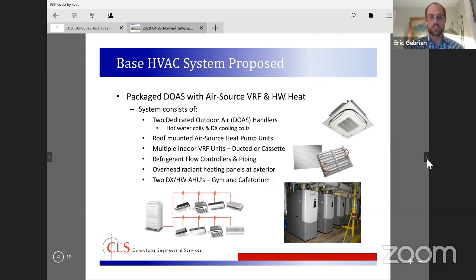Because we're directly ventilating and then directly exhausting each of the classrooms. VRF simply stands for variable refrigerant flow. If you're familiar with a Mitsubishi ductless split that you might have in your house, or Daikin is another company that makes them, you have a unit on the wall that does heating and cooling, and a unit outside that pairs with it. This is basically a much larger commercial version of that same system. We have multiple indoor units, one for each classroom, and multiple outdoor units that work together. That's the system we're using more and more these days because it's become extremely efficient at heating and cooling, far more efficient than existing systems in schools that are 10, 20 plus years old. It's got great turndown for part load heating and cooling, and there's a lot of flexibility in how you can configure it.